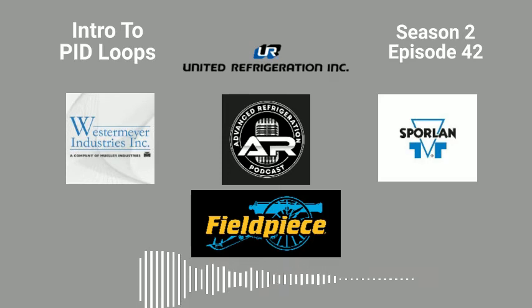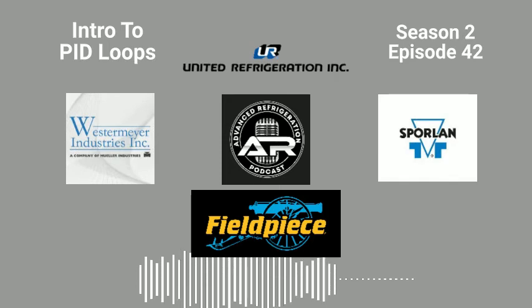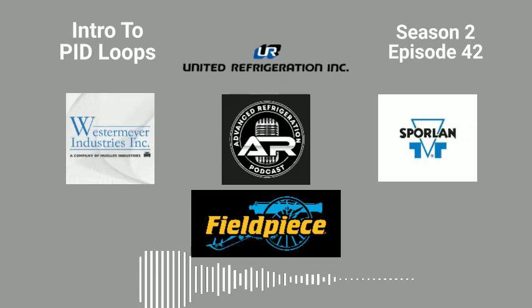Brett, have you messed with much Danfoss stuff, like for the PID tuning? No, sir. I haven't really messed with much Danfoss stuff besides the CO2 controls, but Micro Thermo is the same thing. Micro Thermo uses base values too, so that adds something in there. It starts out with a base value. Say you may have a 20% base value, so that may be where its PID loop starts out. You're trying to maintain 20% of that loop. So that's one more thing to throw in there.